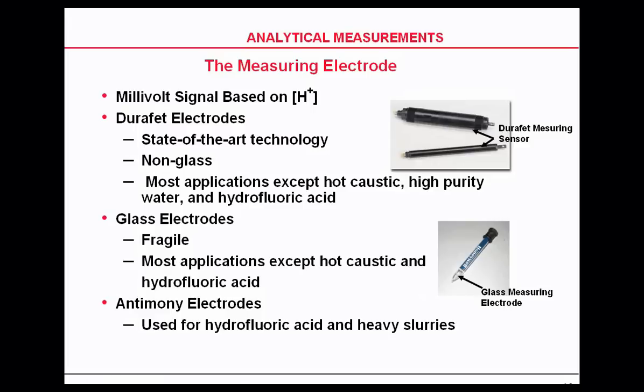As we get into the high-purity conversations, you'll see why you wouldn't use a DuraFET in hydrofluoric acid. Hydrofluoric acid will etch the FET just like it would etch glass. Glass electrodes are fragile. They'll do all the applications except hot caustic and hydrofluoric acid. Hot caustic, and we're talking about 12 pH at 180 degrees or hotter, will also etch glass.